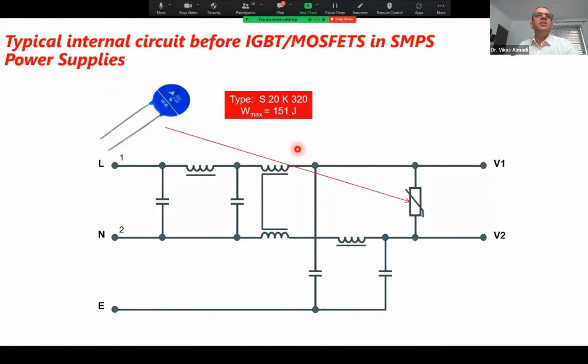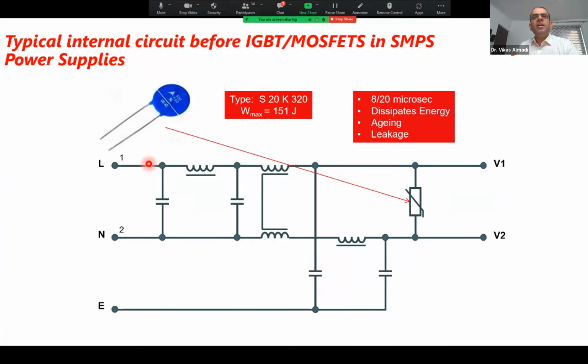to 151 joules. This is an extract of a data sheet from EPCOS, a Siemens company, one of the best: 151 joules. Now you have seen that in case of lightning, we are talking about megajoules, and it can carry a wave shape of 8 by 20 microsecond. It dissipates the energy, it heats, and every time it leaks. It's a kind of variable resistance. The more voltage you apply across this, that means if the impulse is increasing, the lower its resistance. So every voltage exposure ages this device. The performance next time will not be the same. It will deteriorate, and it will die out sometime because of the aging effect.